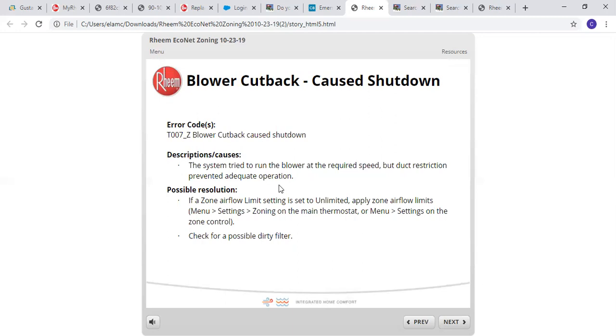It'll say most of those are 66. If you're getting a blower cutback situation, that means your static pressure is exceptionally high and the motor recognizes that it can't run at its required blower speed because of the restriction. Possible resolution: if a zone airflow limit is set to unlimited, you can apply airflow limits to that. Menu settings, zoning.